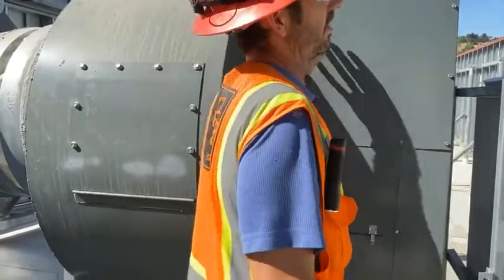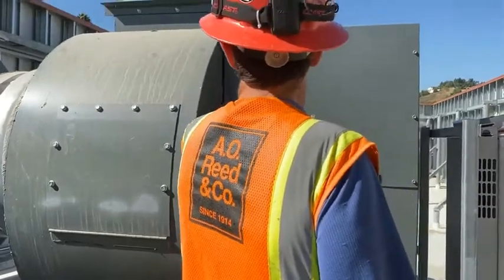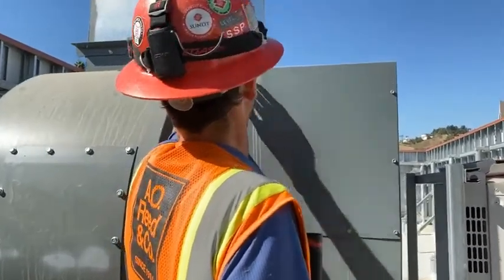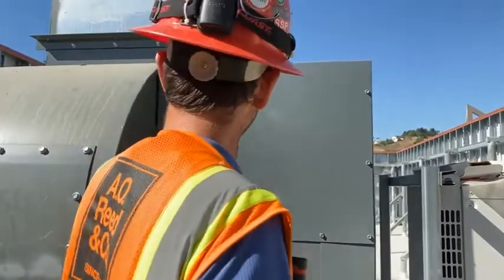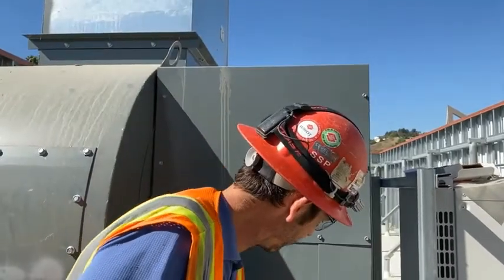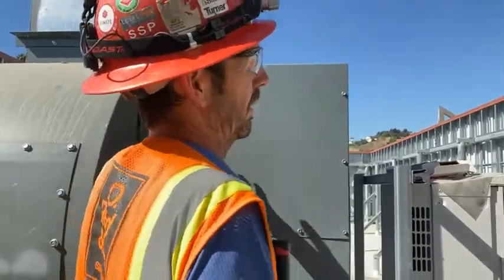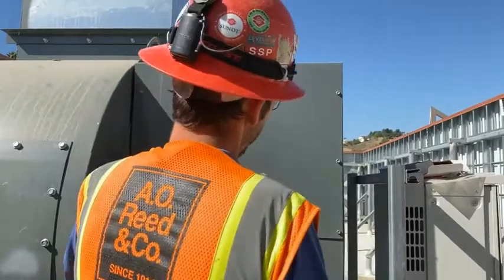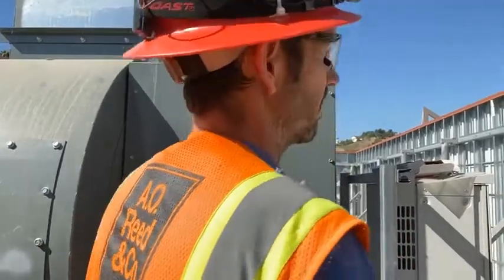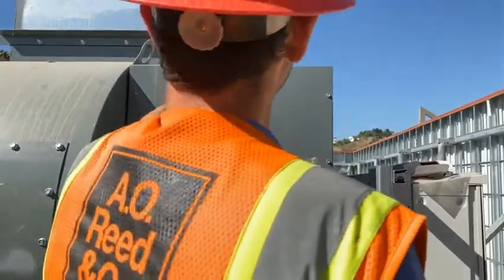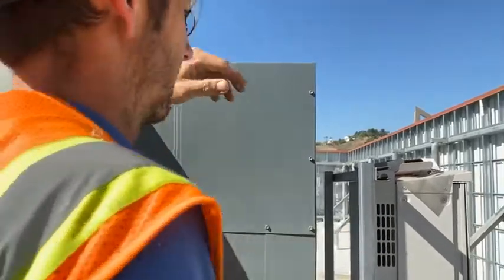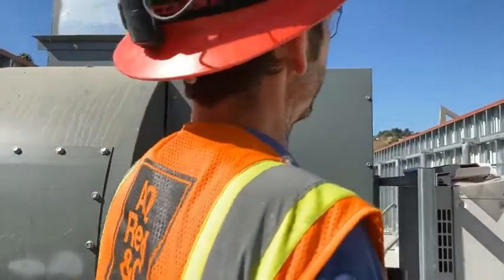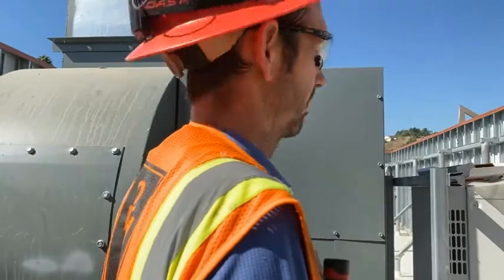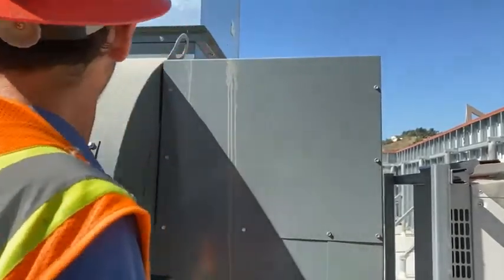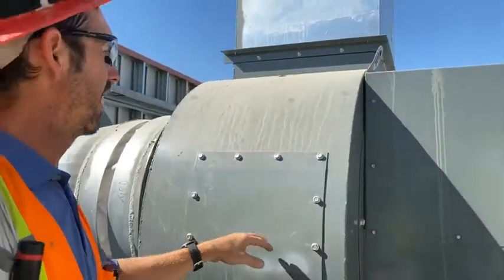This unit does have greasable bearings too. All these screws around the top, there's 3 on the top and all the ones on the side right here, these can just be loosened. It's going to take 2 people to get this cover off, okay? The cover will slide off and then come towards me, okay? 2 greasable bearings at the top of this. Same grease, same manufacturer, okay? This is an inspection port for the wheel itself.